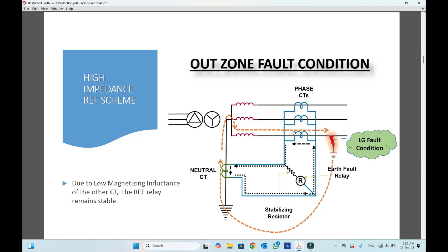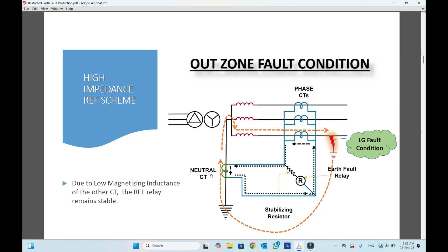This current will take a circulating path because both currents are equal — whatever current passes through the blue phase CT, the same current will flow through the neutral CT. This means both secondary currents will be the same. The neutral secondary current and the unbalanced secondary current will be the same. Due to the low magnetizing inductance of the other CT when primary current is flowing, instead of taking the high impedance path of the relay and resistor, the current will take the low impedance path provided by the CT. So the relay will be stable in this case.